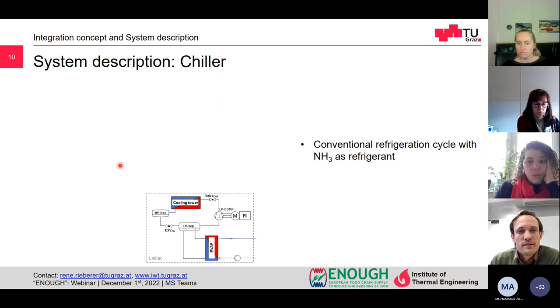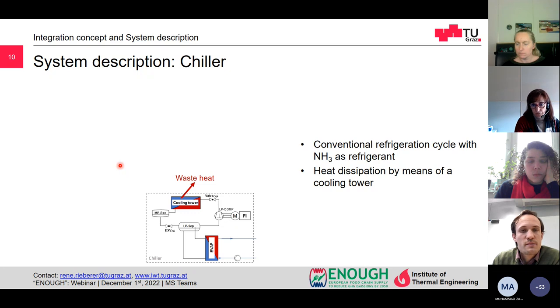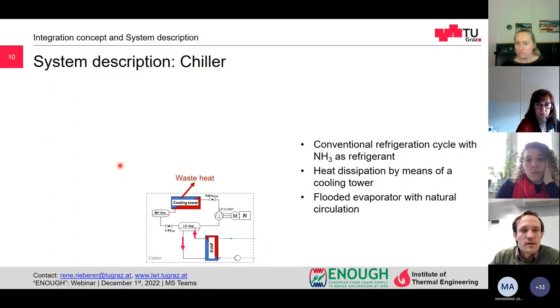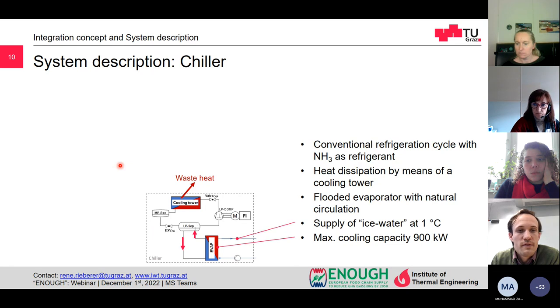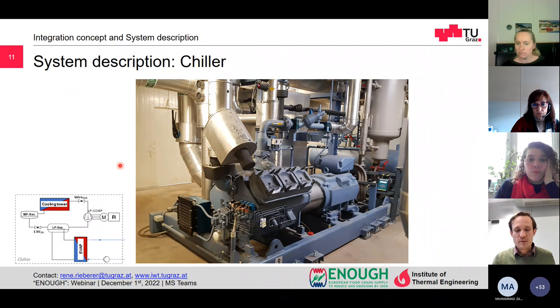A more detailed description of our system. We have here this conventional refrigeration cycle. For the original system, the heat was dissipated by means of a cooling tower. The chiller uses a flooded evaporator with a natural circulation. And in the evaporator, the ice water is supplied at around 1 degree Celsius with a maximum cooling capacity of 900 kilowatt.